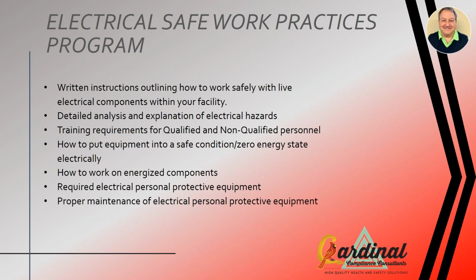Also, how to work on energized components needs to be part of your system. Maybe you're going to have a decision level of Category 2, Category 3, Category 1. What level of PPE do you as an employer want to supply? What do you feel safe for your electricians working on? And you put a self-imposed internal limit on and say, my people have the equipment and the training to work up to Category 2. Anything beyond that, I'll call in outside people. Some of the electrical gear can be a little expensive, and if you're not using it all the time, it may not be the best investment. So that's why you have to provide the electrical gear, the PPE, the arc flash gloves, the voltage gloves, whatever level of suit and protection is required to work in the different categories.